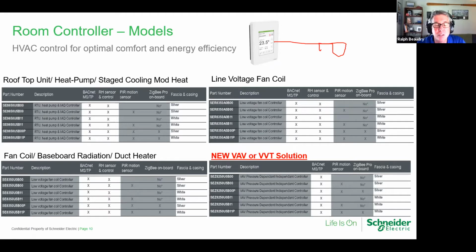And we have some new models we just added into the product family called the SEZs. They're a true pressure-independent VAV or a pressure-dependent VVT solution. Either way, our VAV solution is a remote damper actuator and velocity pressure sensor that you mount at the unit. You run an 8-conductor cable back down to the SEZ and do your wiring, and you've got commissioning from the floor. So you put in your K factors. You can set mins, maxes from the floor. You can drive the dampers, all those sorts of things.